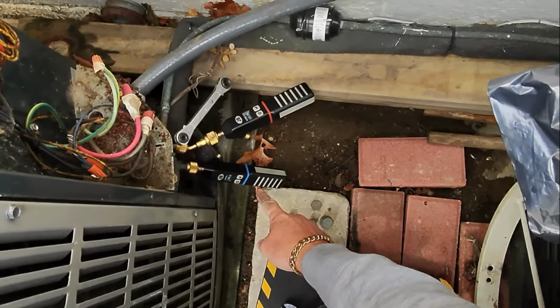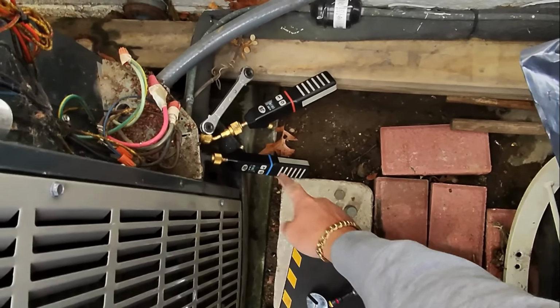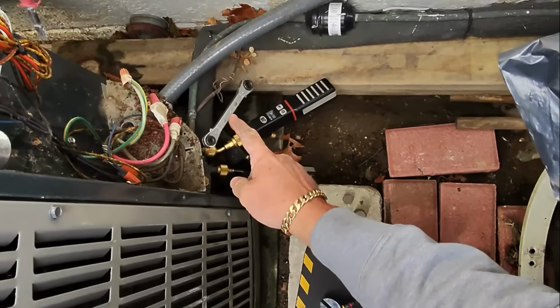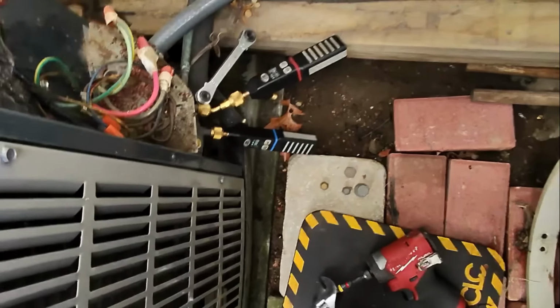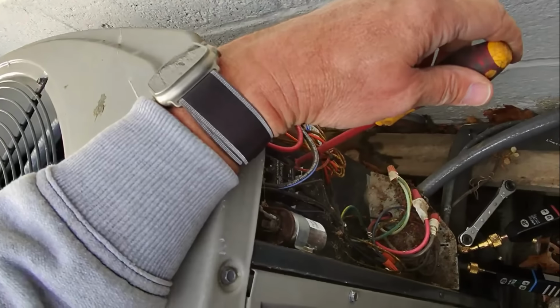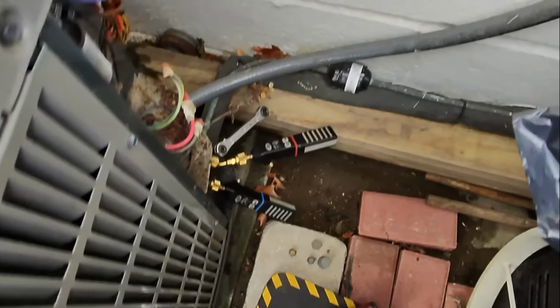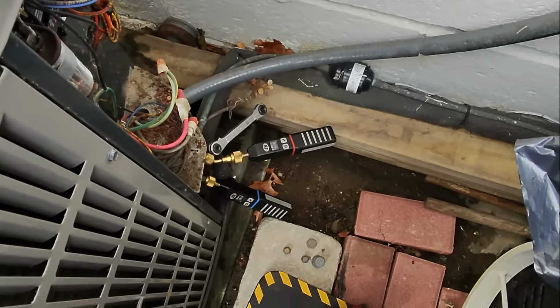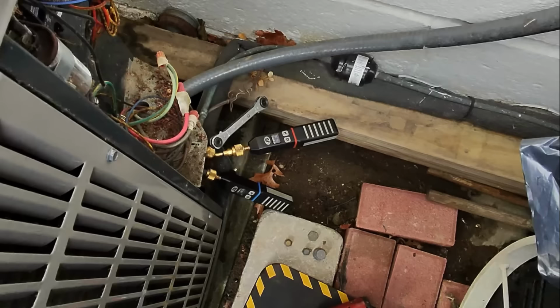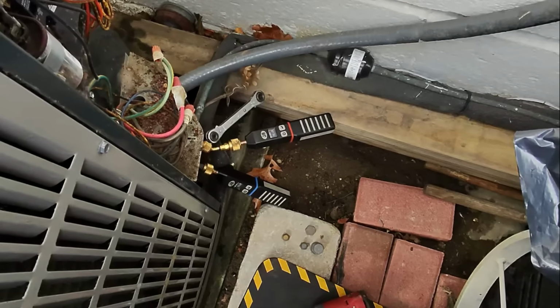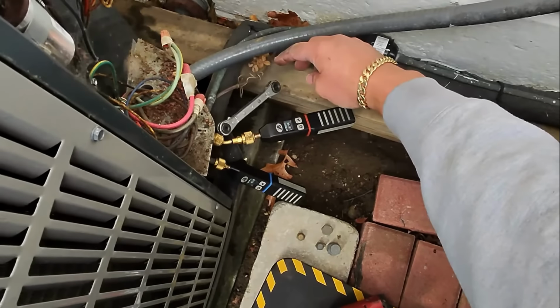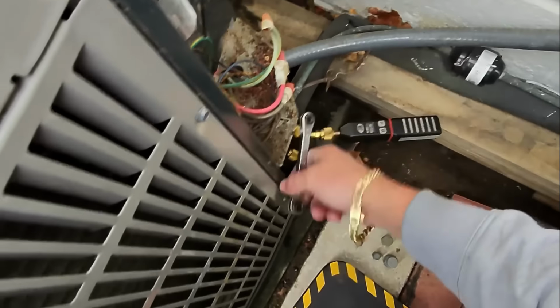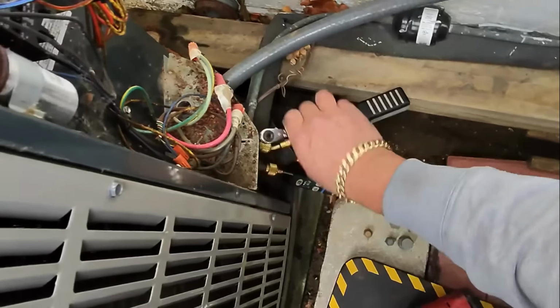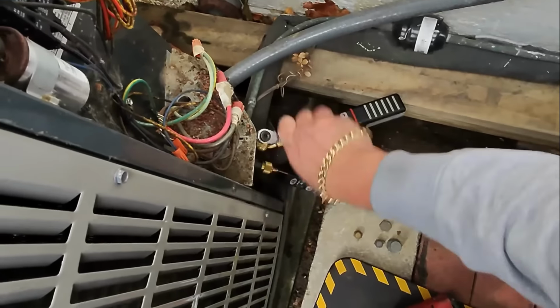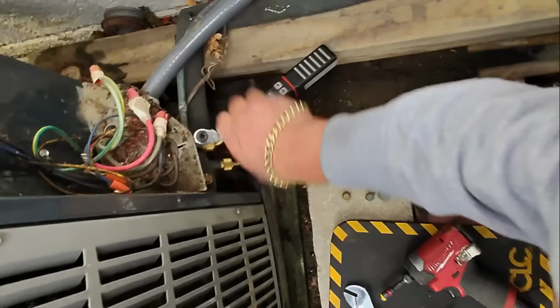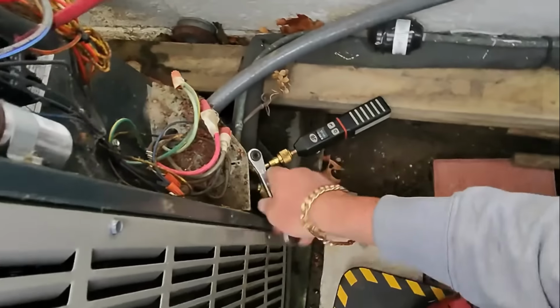All right, I got my JB Climate Class probe set up to my low side and my high side. I got my service wrench ready. I got a regular wrench ready to close that valve. Let's fire up. 93, 92. Our pressure is... pressure's actually increasing there, so let me close this valve. We'll see how low we can go before she cuts off on compressor bypass.